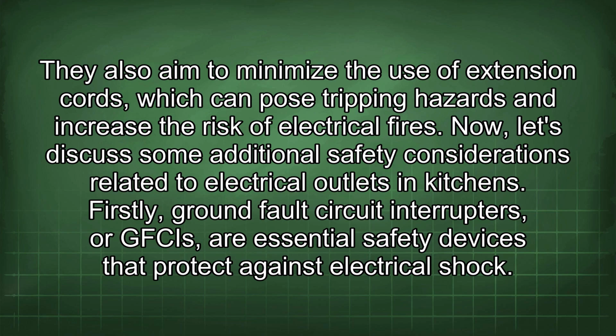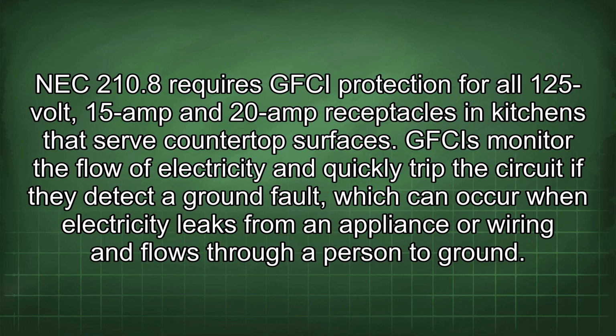Firstly, ground fault circuit interrupters, or GFCIs, are essential safety devices that protect against electrical shock. NEC 210.8 requires GFCI protection for all 125 volt, 15 amp and 20 amp receptacles in kitchens that serve countertop surfaces. GFCIs monitor the flow of electricity and quickly trip the circuit if they detect a ground fault, which can occur when electricity leaks from an appliance or wiring and flows through a person to ground.